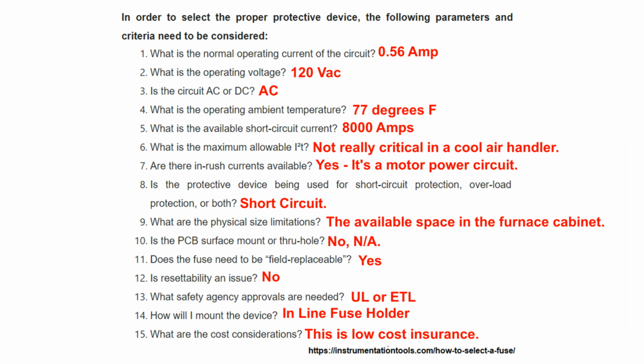What are the physical size limitations? Well, there's a small amount of space available in the cabinet, and I'm installing a small fuse, so it isn't a problem. Is the PC board surface mount or through hole? This isn't a PC board mounted fuse, so it's not applicable. Does the fuse need to be field replaceable? Yes. Is resettability an issue? No. What safety agency approvals are needed? I like UL or ETL. How will I mount the device? Well, this is an inline fuse holder. What are the cost considerations? I consider this to be low-cost insurance.